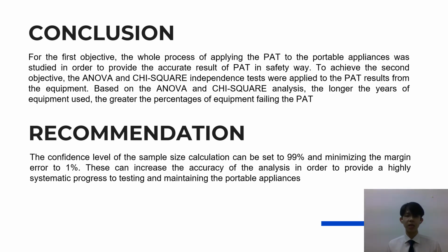failing the PAT result. Other than that, we recommend that the confidence level of the sample size calculation be set to 99% and the margin of error minimized to 1%.